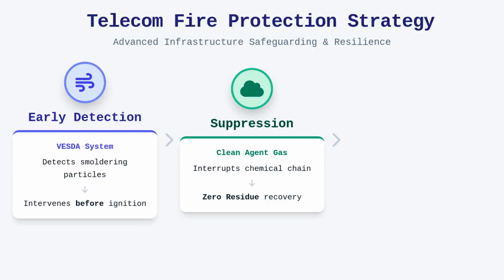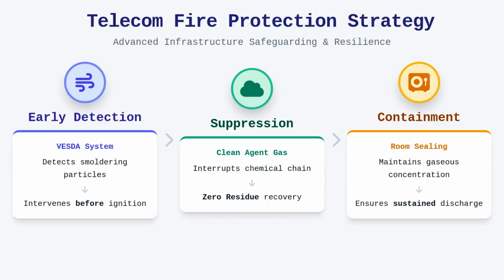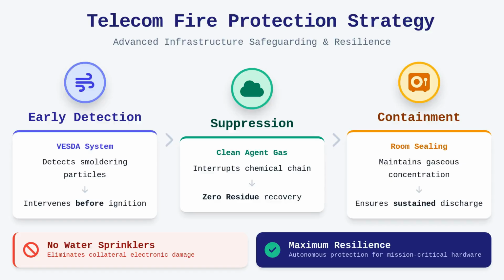The design must also account for room sealing integrity, as the effectiveness of the gaseous system depends upon its ability to maintain the required concentration for a sustained discharge period. By integrating these detection and suppression technologies, we create a secure, autonomous environment that protects infrastructure against both thermal degradation and the catastrophic potential of fire, ensuring long-term resilience for the networking hardware housed within.